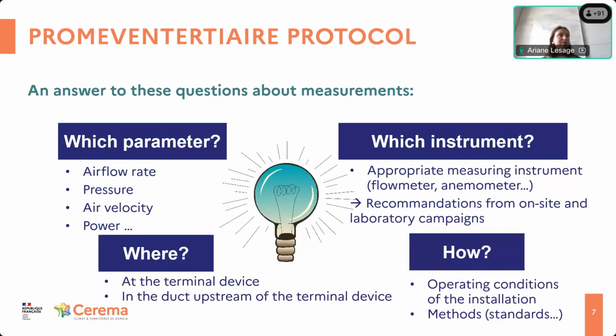So which parameter should be measured? Is it airflow rate, pressure, air velocity, power? Which instruments can be used? It is important to use the appropriate measuring instrument, for instance, flow meter, anemometer, and PromevenTertiaire gives some recommendations from on-site and laboratory campaigns to indicate which is the most appropriate following the various situations. Where can the measurement be done? Is it at the air terminal devices or in the duct upstream of the terminal device? And how? Which are the operating conditions of the installation, and what are the methods based on standards or good practices?